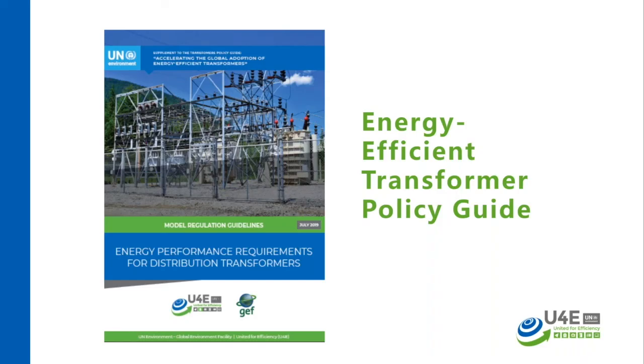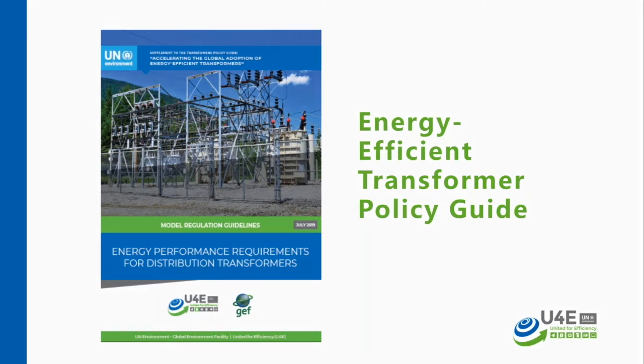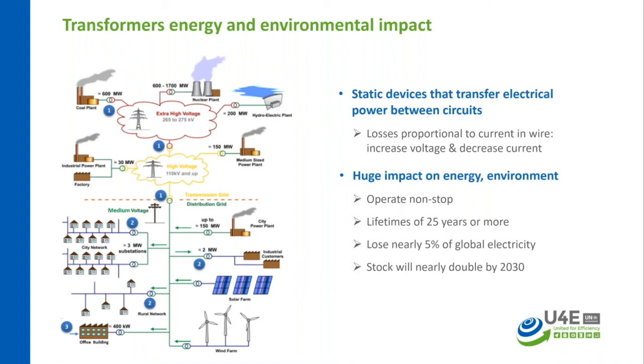So the document will look like this, and it will contain the details, as Sol mentioned, in terms of all the attributes related to the environment friendly and energy efficiency performance management of transformers. As you all from the transformer industry know, in Mozambique you have voltages right from 400 kV, which is the highest transmission voltage in Mozambique, connecting with the neighboring countries at that high voltage. So the utility assets start from 400 kV up to the lowest voltage of 6.6 kV in some of the areas, the distribution voltage, and then the voltage at the user end is 440 volts like the IEC standard.